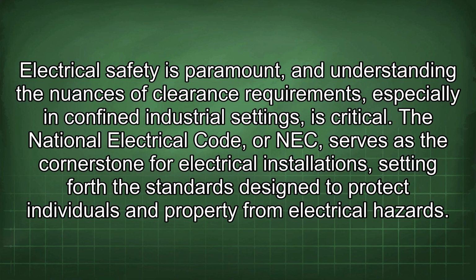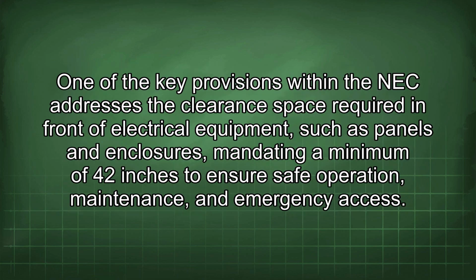The National Electrical Code, or NEC, serves as the cornerstone for electrical installations, setting forth the standards designed to protect individuals and property from electrical hazards. One of the key provisions within the NEC addresses the clearance space required in front of electrical equipment, such as panels and enclosures, mandating a minimum of 42 inches to ensure safe operation, maintenance, and emergency access.